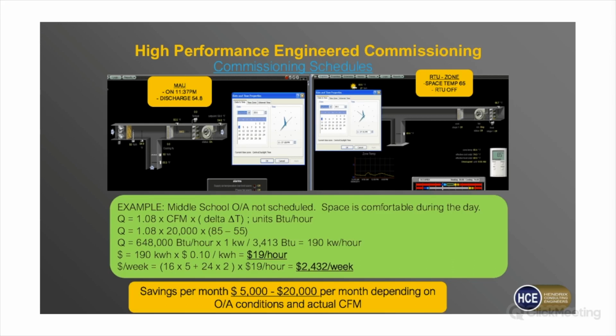And so, you may not think that's a ton of energy, but this particular outside air machine or group of outside air machines, a school could easily have 10 or 20,000 CFM of outside air. The equation for that energy is 1.08 times the CFM times the delta T. So in that school, in this example, there was 20,000 CFM. The delta T, it was about 85 outside. It was cooling it down to about 55. So there's our delta T. You run all that down and you get BTUs per hour converted to kilowatts per hour.